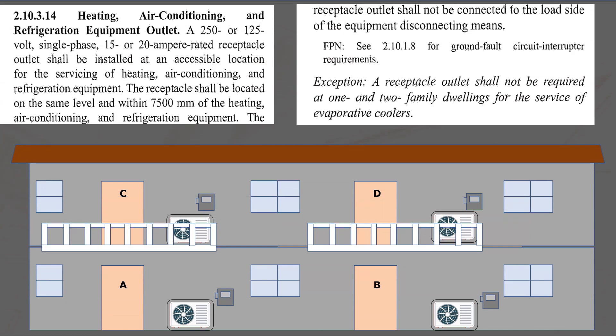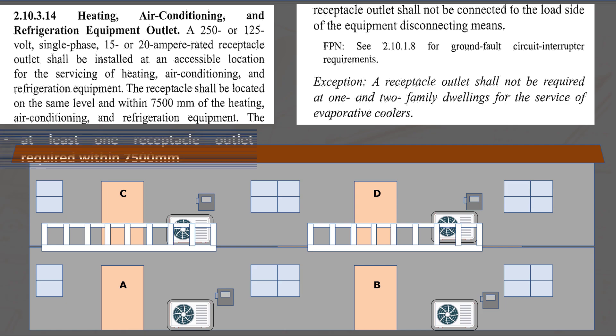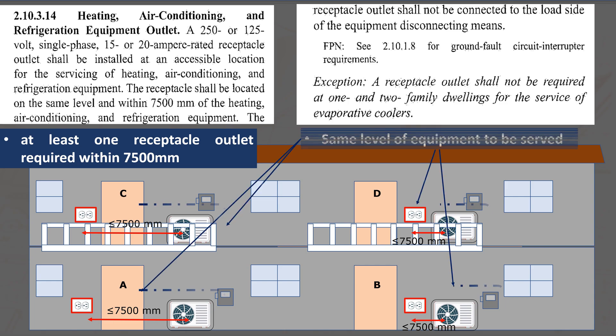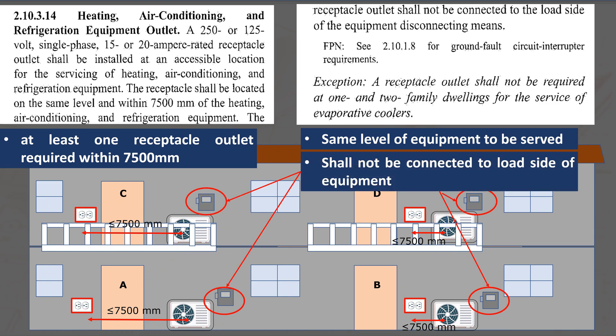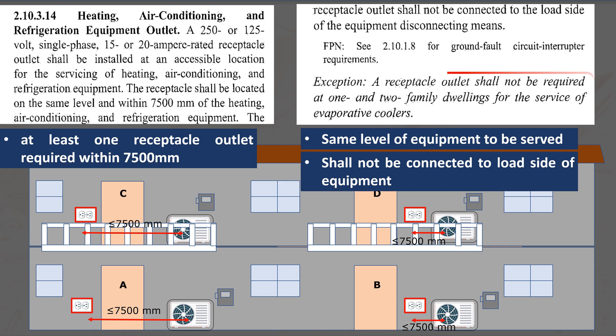Section 2.10.3.14 states that at least one accessible outlet is required for servicing heating, air conditioning, and refrigeration equipment. This outlet must be installed within 7,500 mm from the equipment it serves, and at the same level as the equipment. During equipment repair, the disconnect means will be in the off position for technician safety, so the service outlet must be connected on the line side of the disconnect means, even if connected in the same branch circuit. Evaporative coolers of one- or two-family dwellings are exempted from this section.